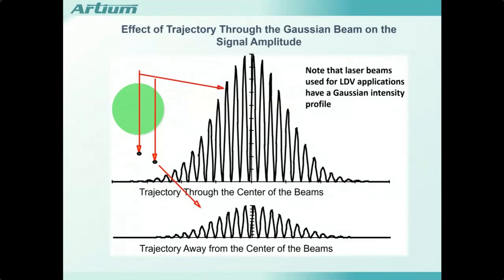The measurements are based on the frequency, and so it's a very strong feature of this method that we really don't care about amplitude, except that amplitude matters in terms of signal-to-noise ratio. If the amplitudes are too low and the background noise is high, it will be difficult to process these signals, and I'll get into talking about that later.